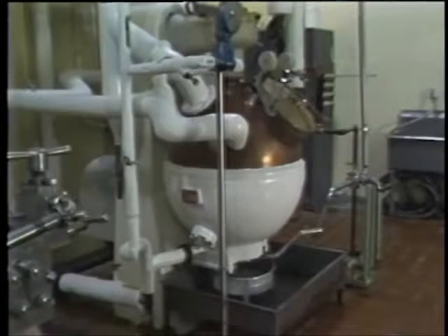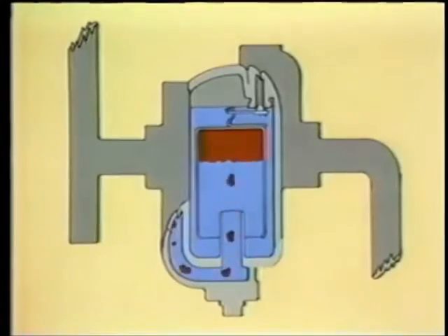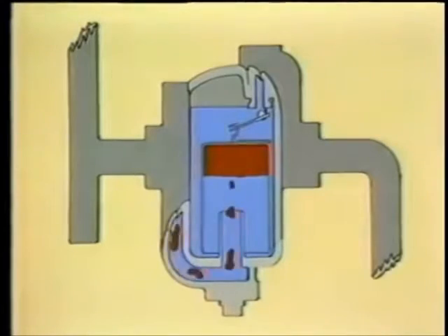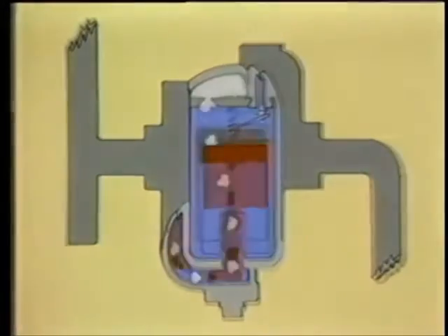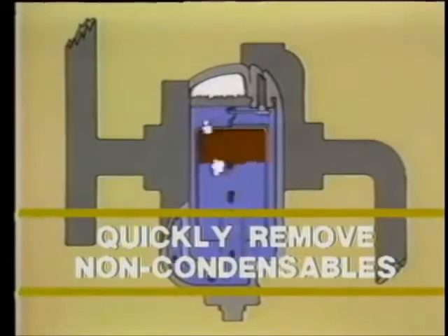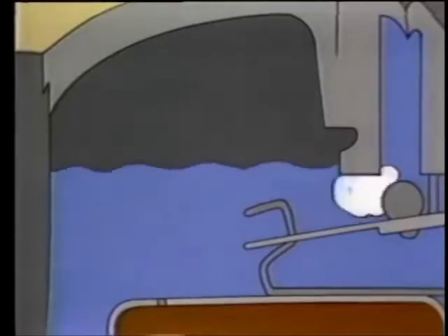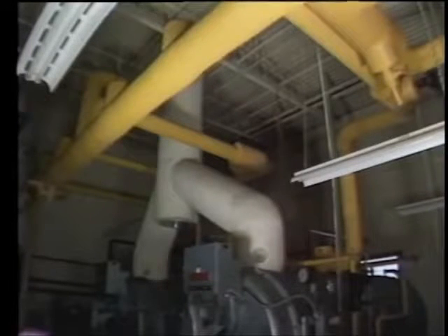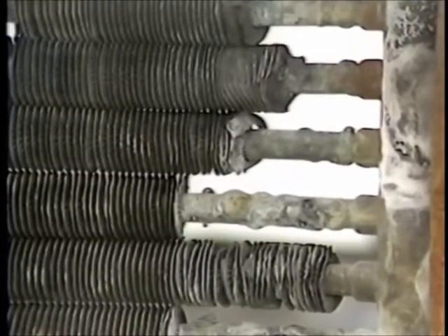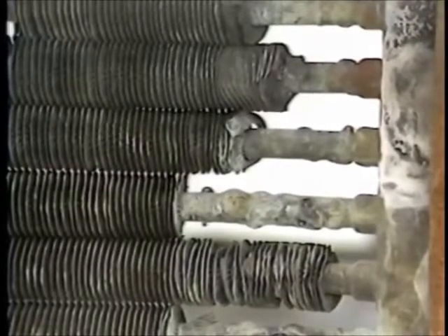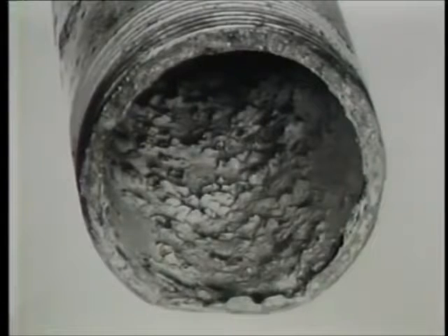Efficient use of steam with heat exchange and process equipment requires proper trapping. The job of the steam trap is to get the condensate and non-condensable gases out of the steam space as fast as they accumulate. The condensate must be removed quickly or it will reduce the performance or heat transferability of the equipment. Non-condensable gases must also be removed at or near the saturation temperature of the steam. Oxygen and carbon dioxide are released in the boiler when steam is produced. When CO2 combines with condensate that has cooled below the saturation temperature, carbonic acid will form, which is extremely corrosive. Oxygen in the system furthers this destructive force by causing oxidation.